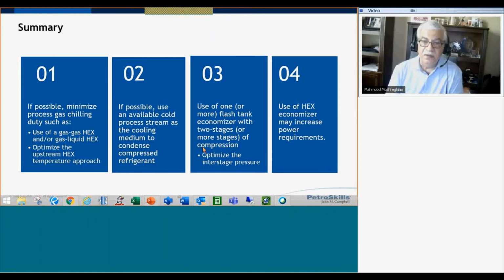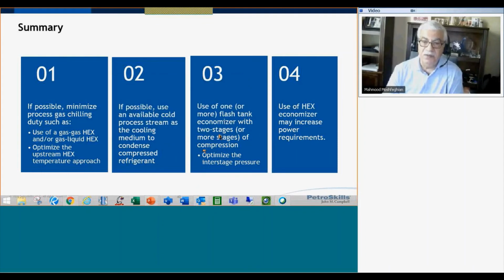Item number 3, use one or more flash tank economizers with 2 stages of compression, or more. Sometimes we use more stages of compression. And also optimize the interstage pressure. We talked about 2 different types of optimizing interstage pressure: equal compression ratio or equal compressor power per stage. And finally, we talked about how use of a heat exchanger economizer may increase power requirement. So if you use that, be aware of it. But if you use an external heat exchanger, an external source for subcooling, it should always work.